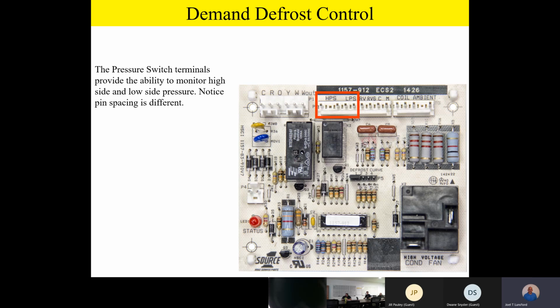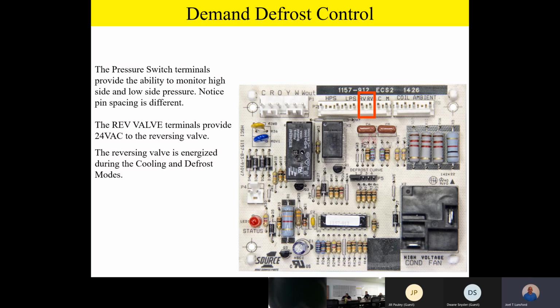Now, it should be noted, all of our heat pumps are going to be coming with a low pressure switch and a high pressure switch for safety. Right next to that, you're going to see there's RV terminals. Those RV terminals are for the reversing valve. And again, it doesn't matter. You'll notice the pin spacing is the same there, so the plug will go either way. It's just a 24-volt output to the reversing valve that we're going to output from the board in the cooling mode of operation for the reversing valve.